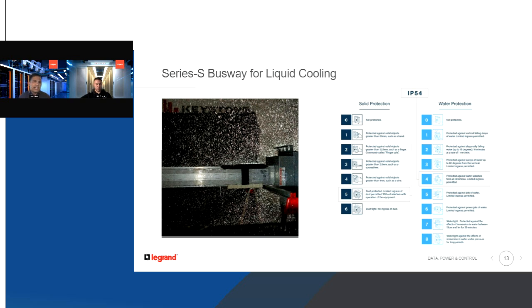Really, the only difference between the S-Series and the T5, the previous busway design that you just viewed, is that once you pick the location of your circuits, you install them into the busway, and we have to seal the bus after the circuit locations and the plugins are installed. Once we seal that bus, we get that extra level of protection against water. Again, we're seeing this shift to liquid cooling because of the increasing power densities, and if liquid cooling is a concern, this S-Series busway is a great way to mitigate that concern.